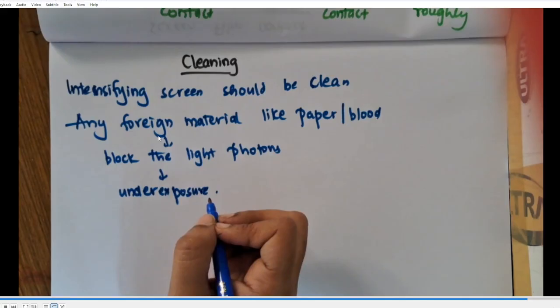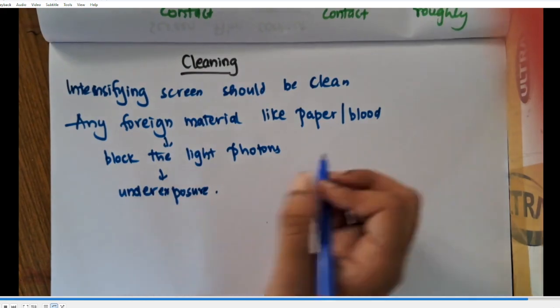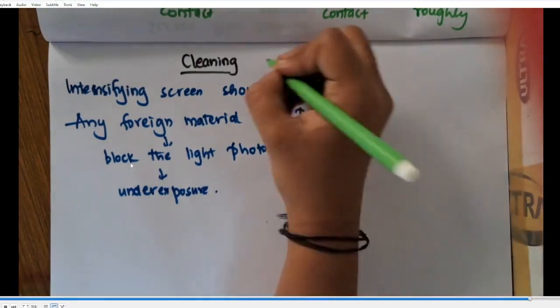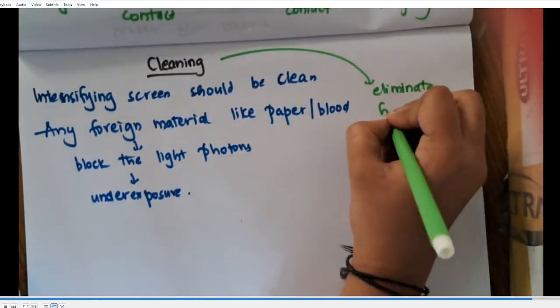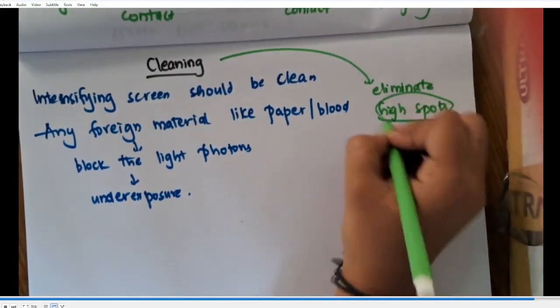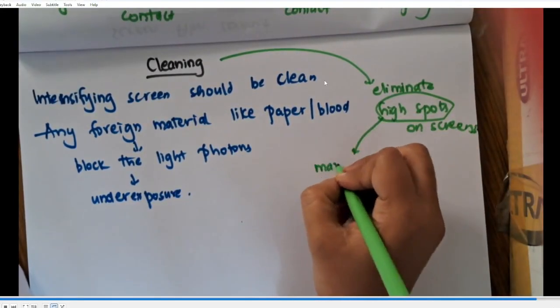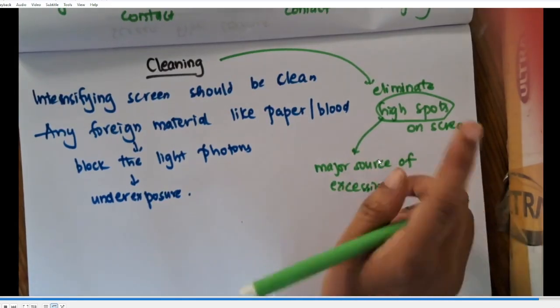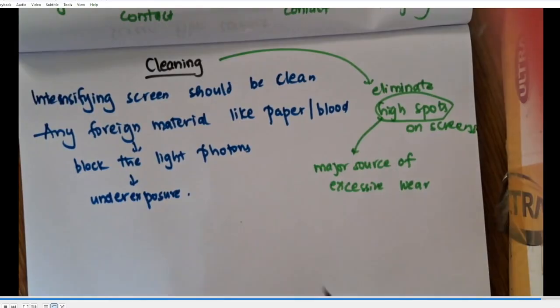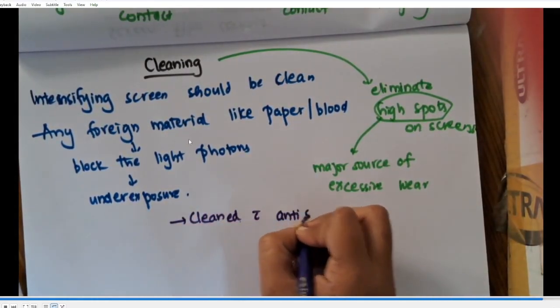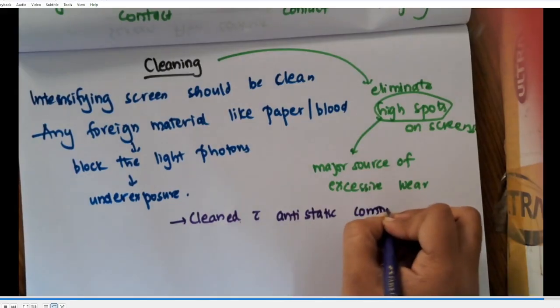So cleaning eliminates the high spots on the screen. These high spots are the high points which are the major sources of excessive wear. The main cause of screen failure is mechanical attrition. Under normal conditions of radiation use, the X-ray photons will not damage the screens.